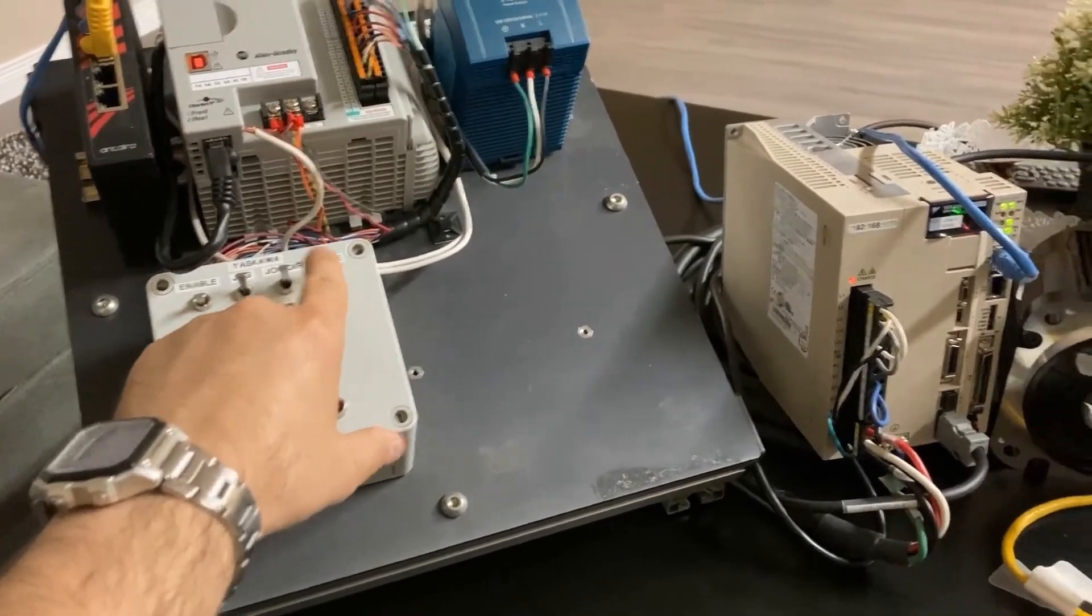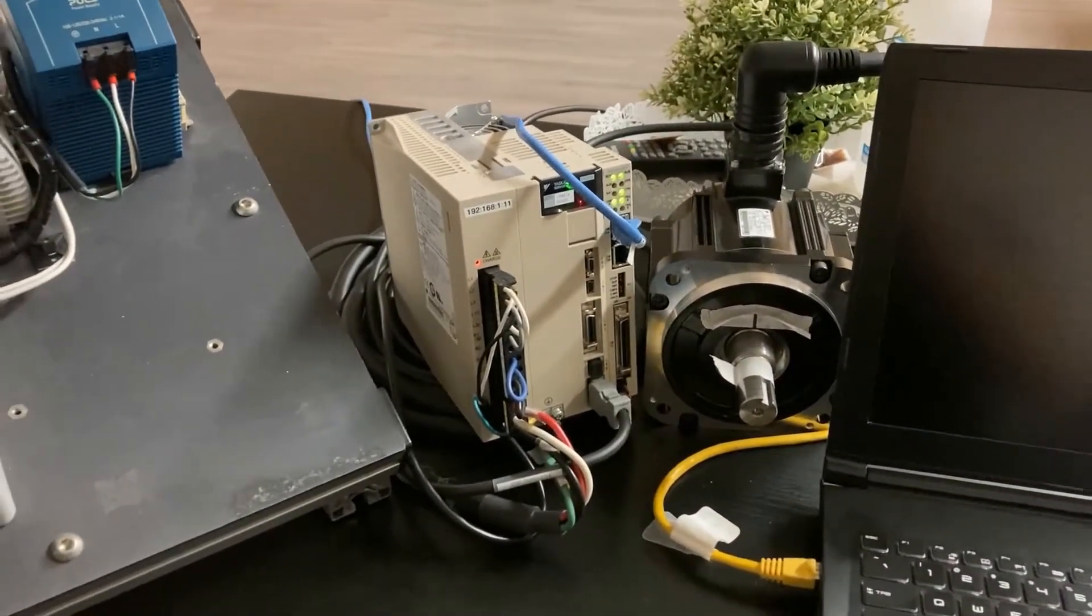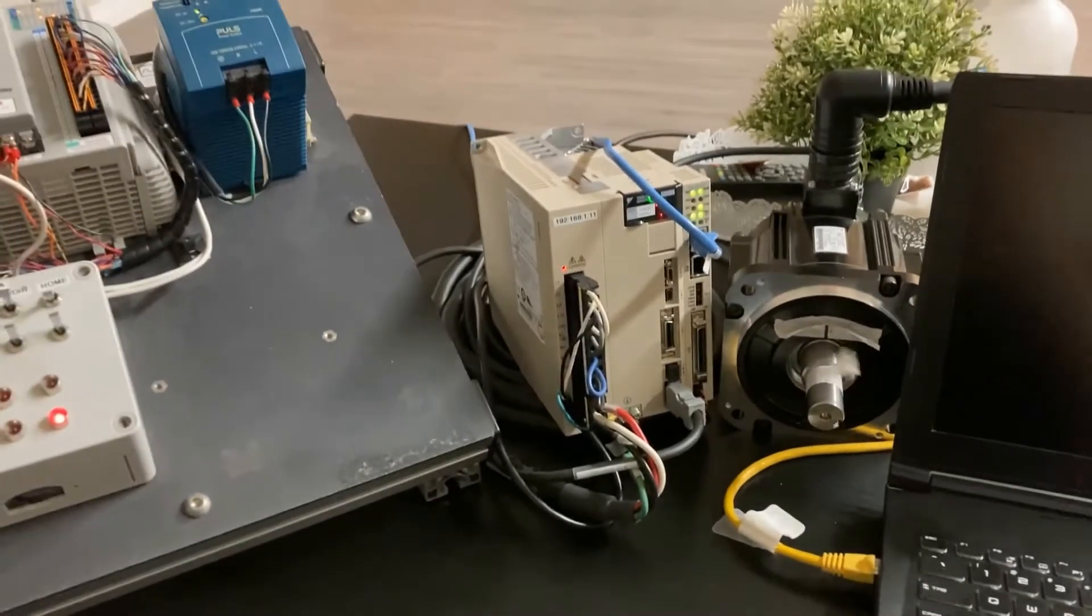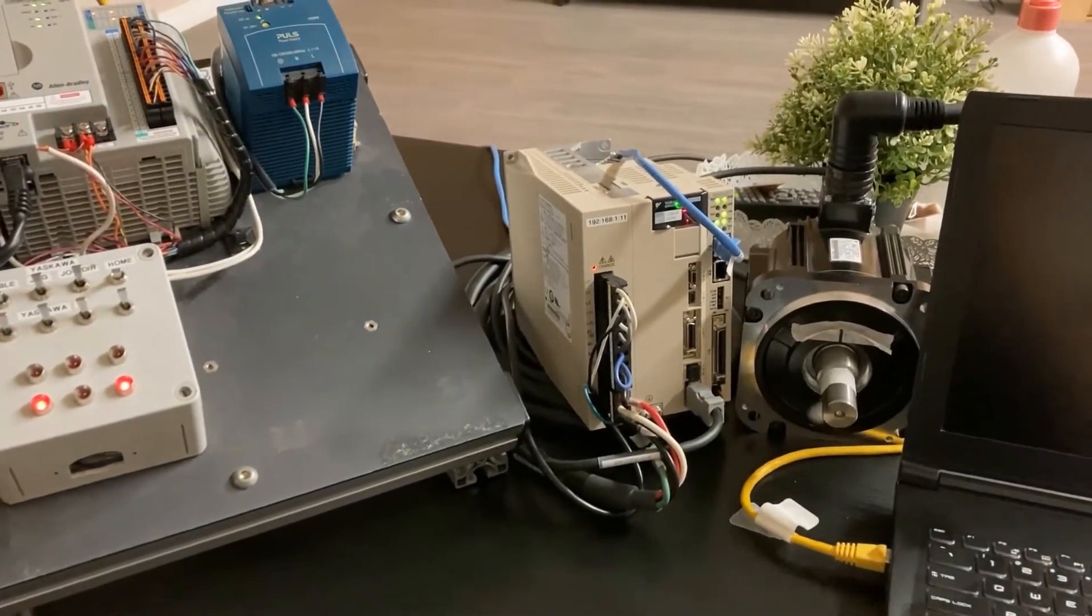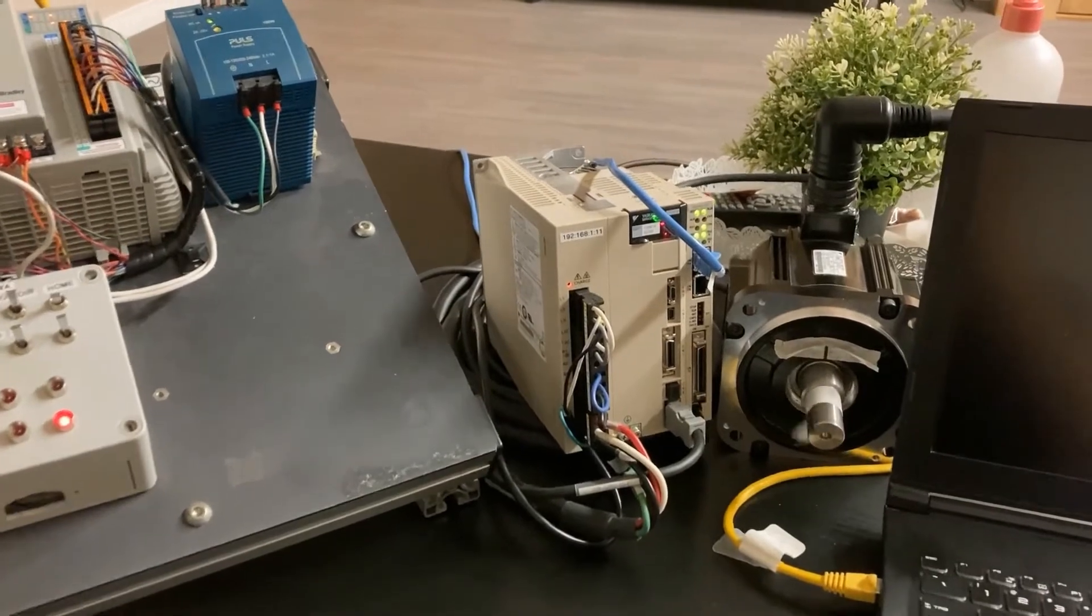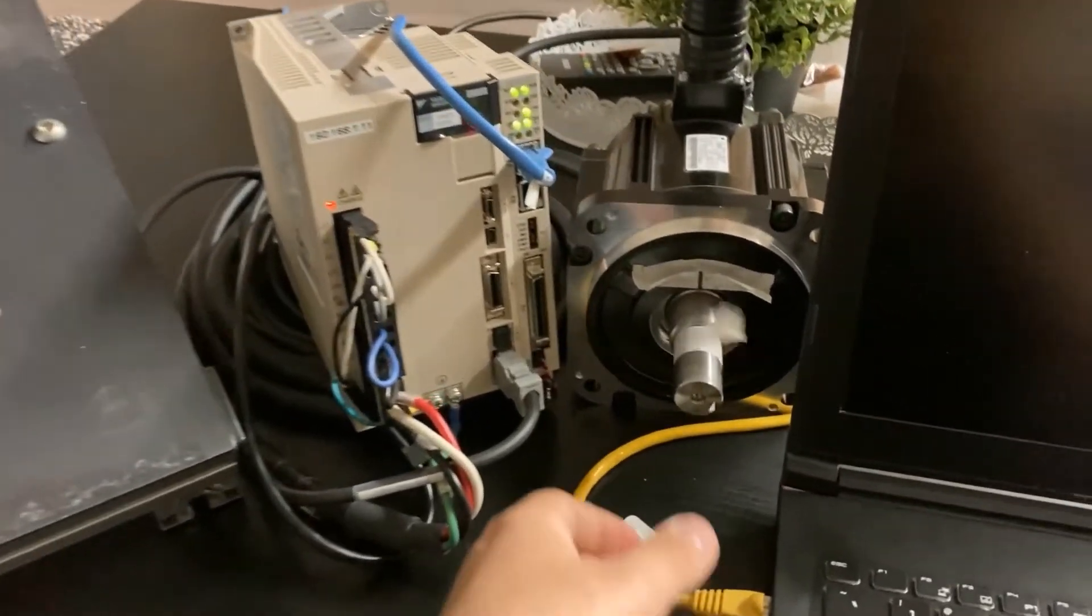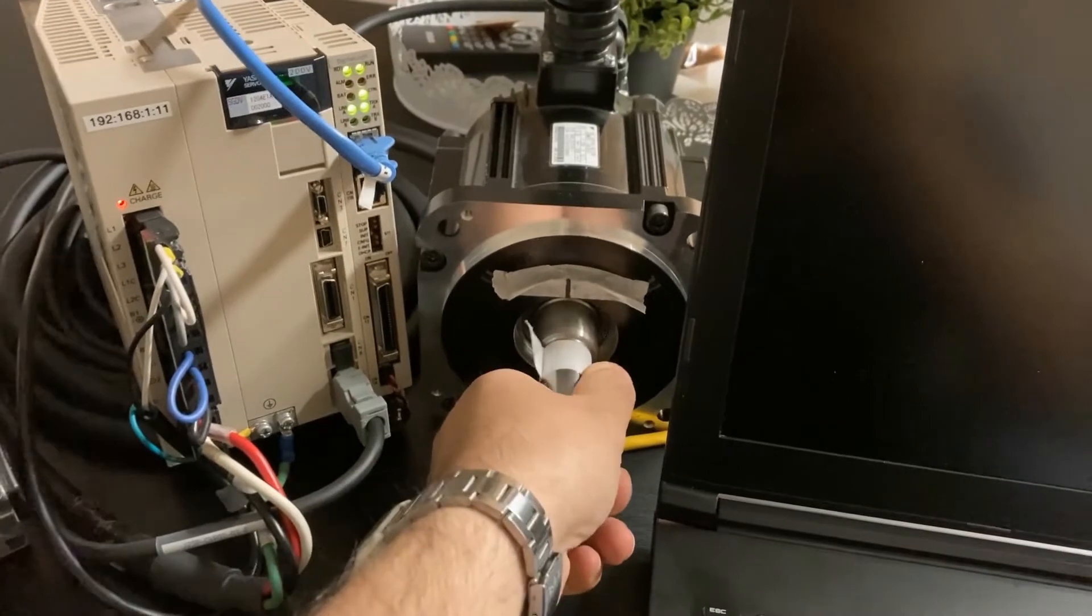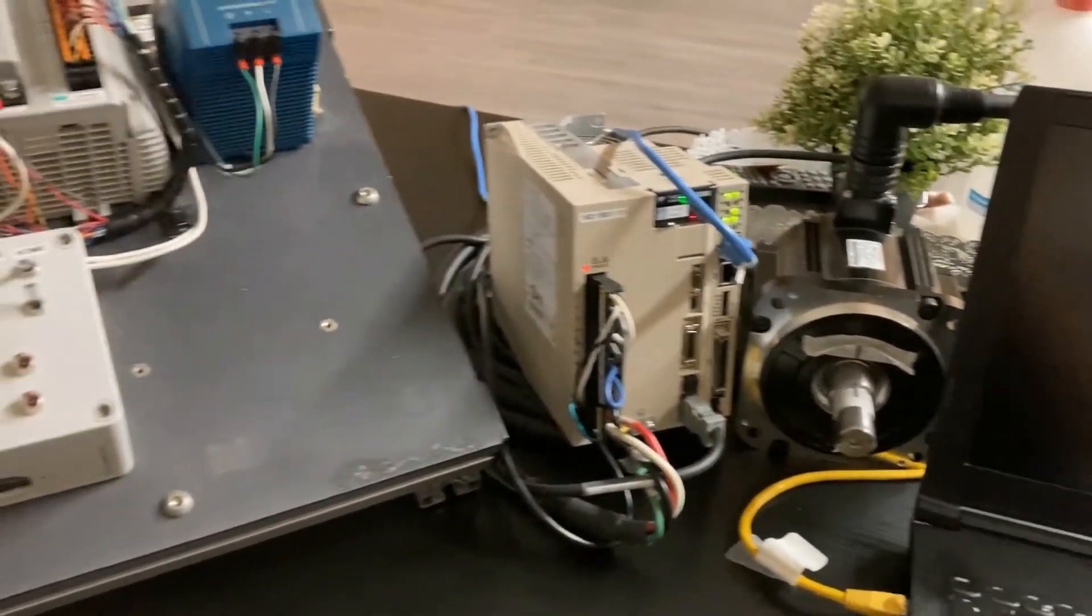With this button here we will trigger the homing. There are a couple of homing methods that can be programmed but the homing method we are using here is home to a hard limit and we will simulate the hard limit using our hand grip so the servo motor will sense the hard limit and will back up to the home position.